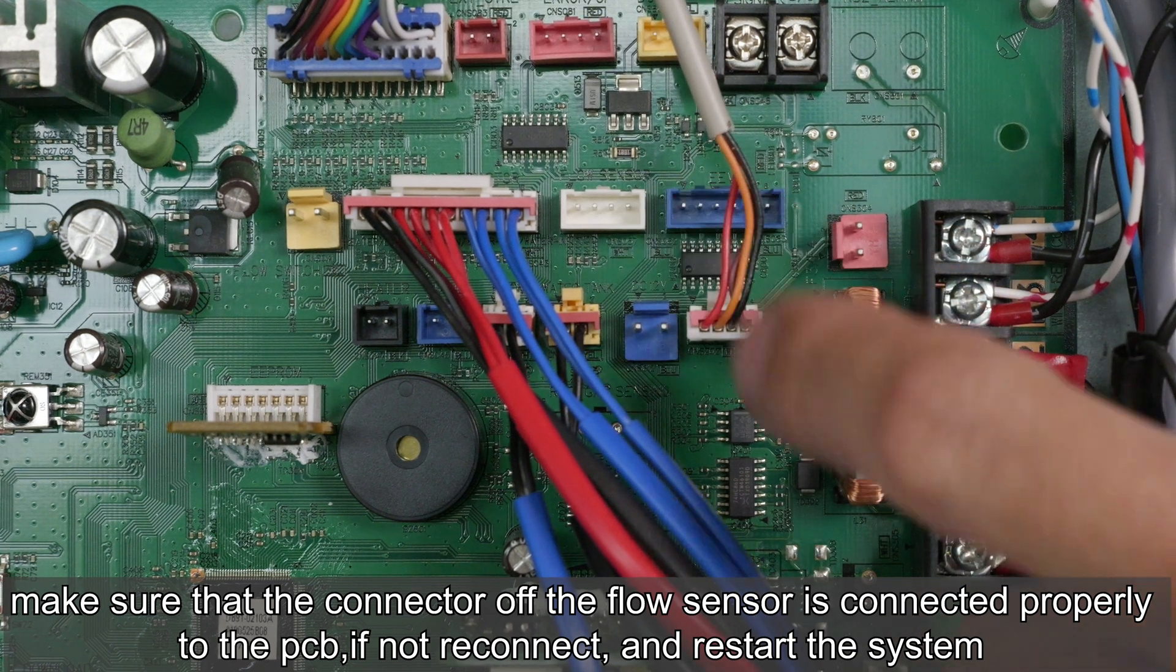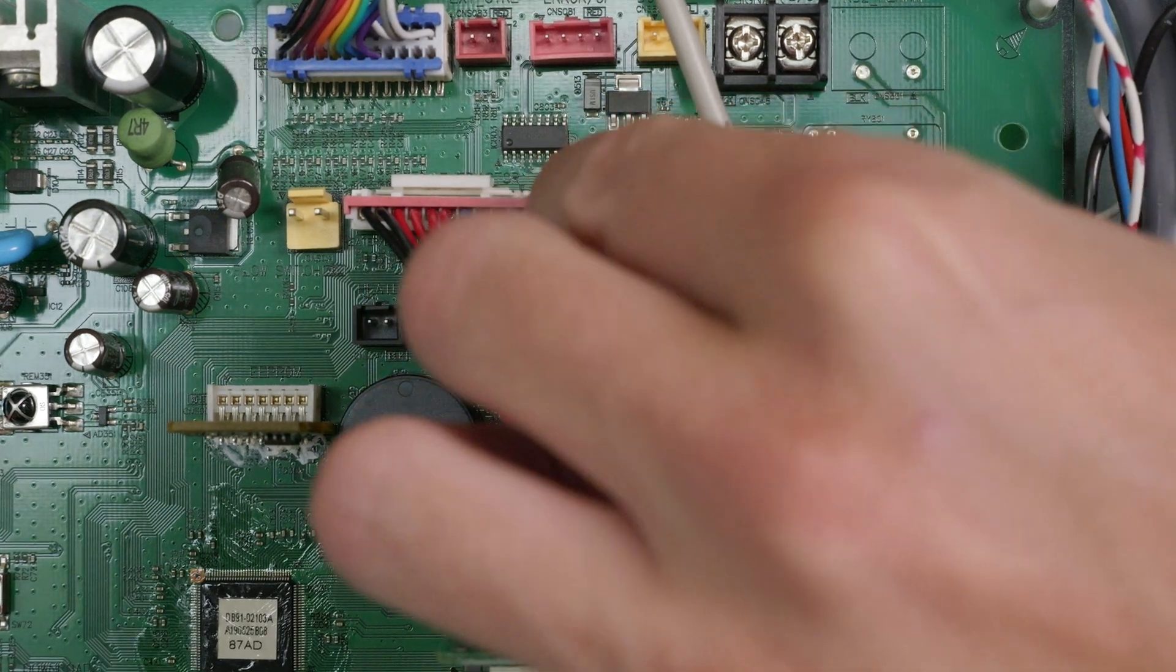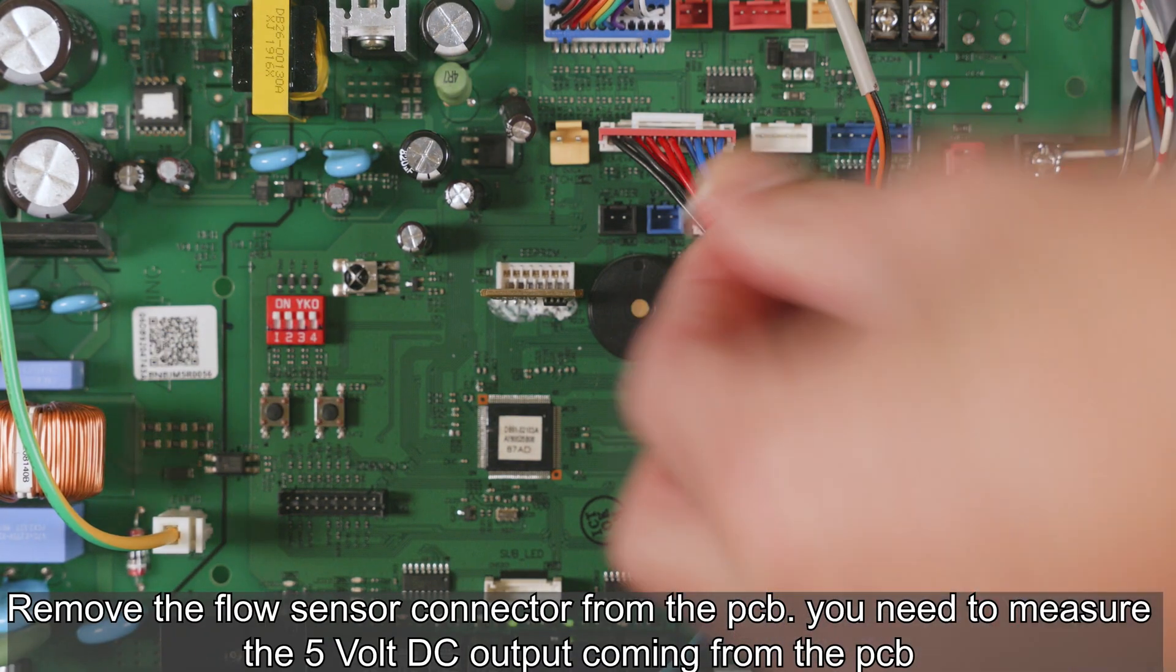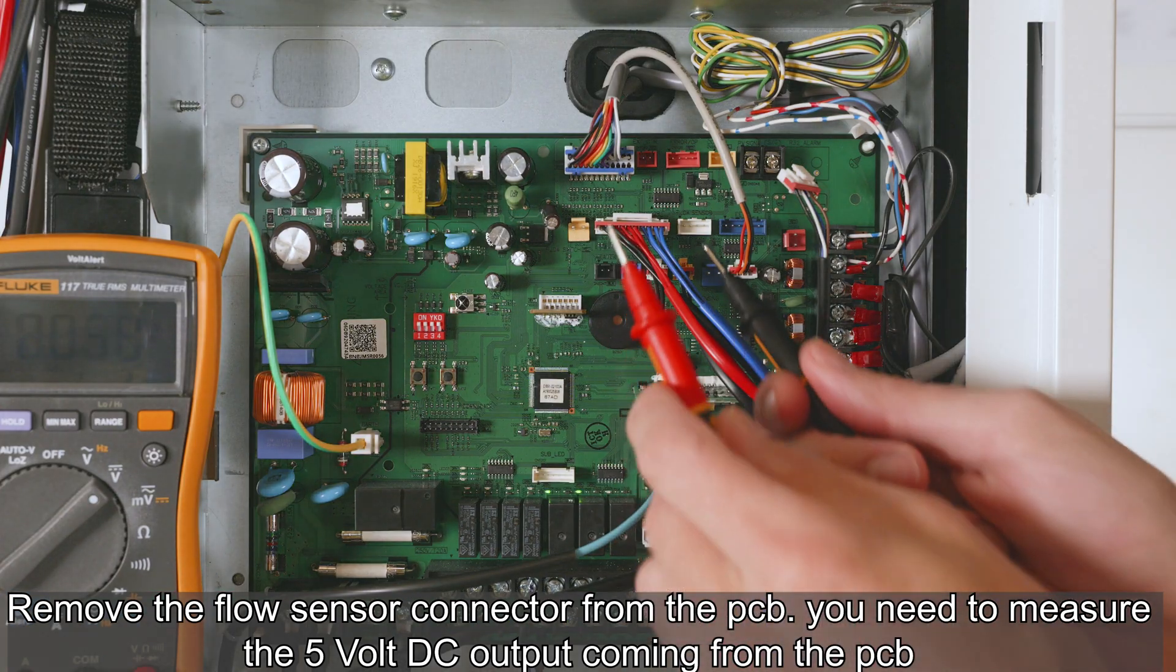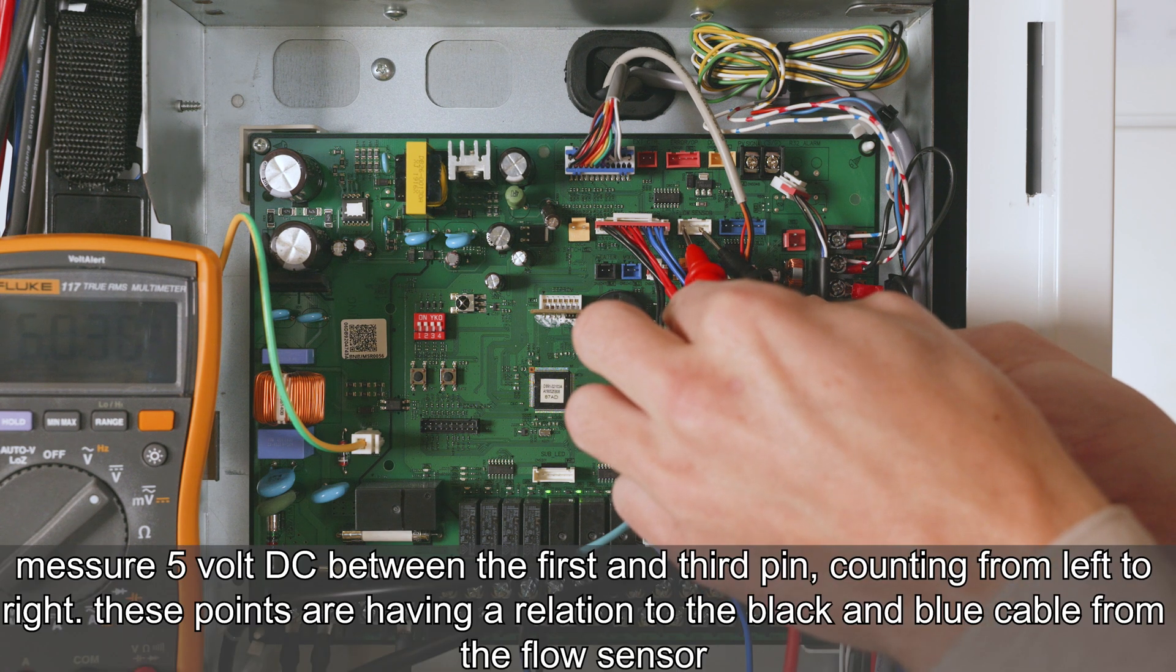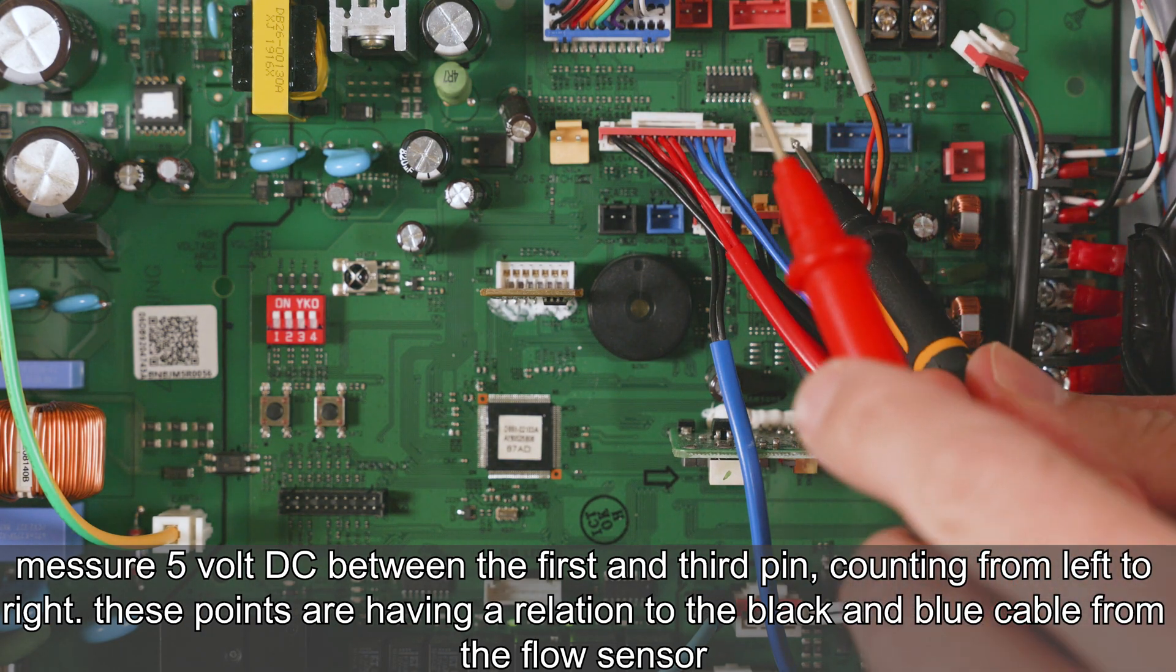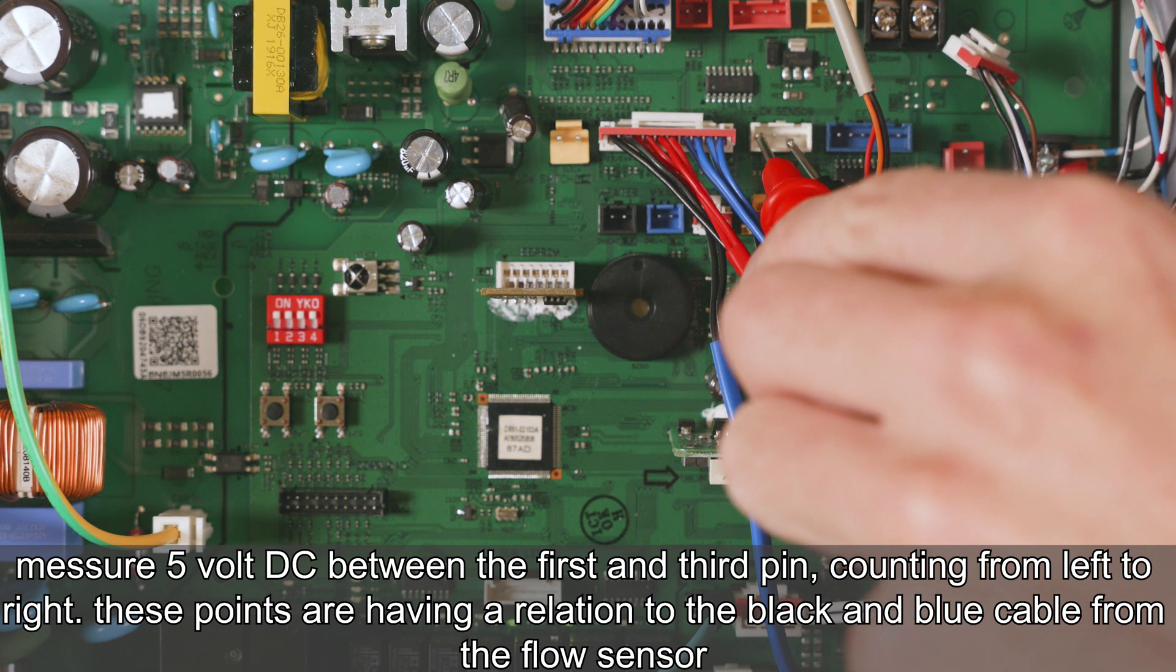Remove the flow sensor connector from the PCB. You need to measure the 5 volt DC output coming from the PCB. Measure 5 volt DC between the first and third pin counting from left to right. These points are having a relation to the black and blue cable from the flow sensor.